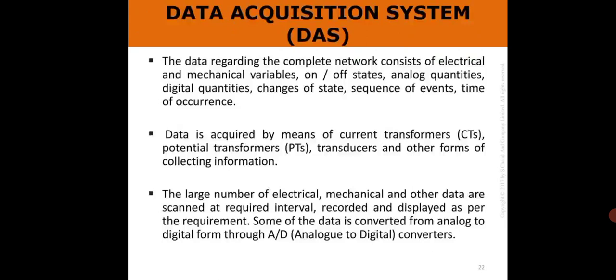Next is the data acquisition system, DAS. The data regarding the complete network consists of electrical and mechanical variables, on-off state, analog quantities, digital quantities, changes of state, sequence of events, time of occurrence. Data is acquired by means of current transformers, CTs, potential transformers, PTs, transducers and other forms of collecting information. The large number of electrical, mechanical and other data are scanned at required intervals, recorded and displayed as per the requirement. Some of the data is converted from analog to digital form by A to D converters.